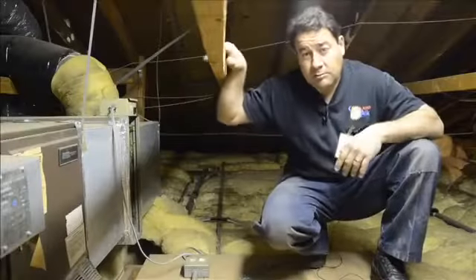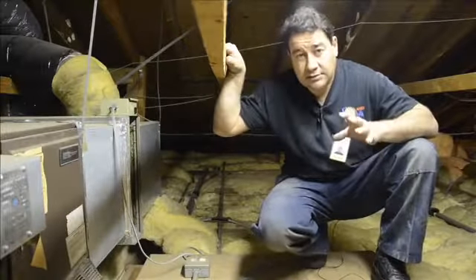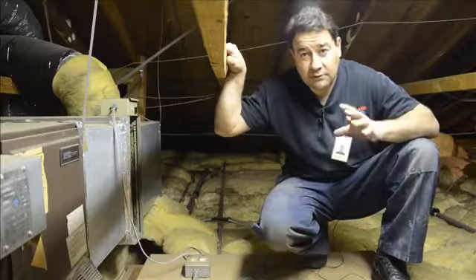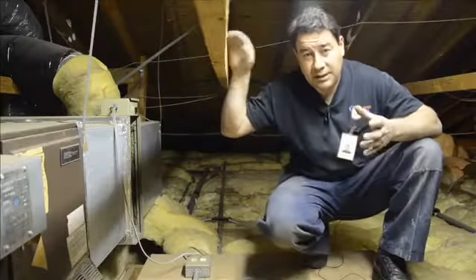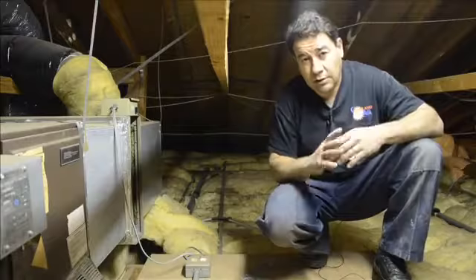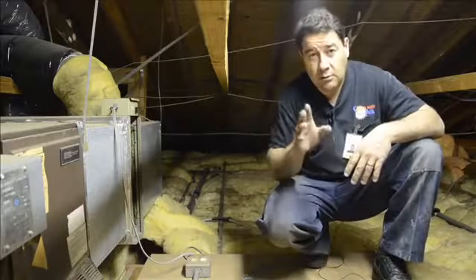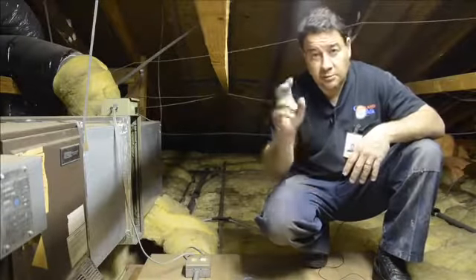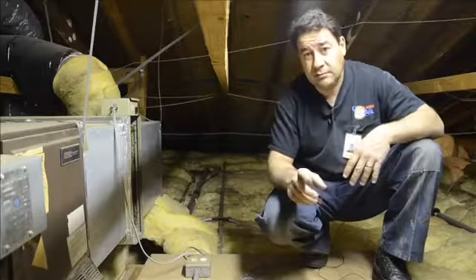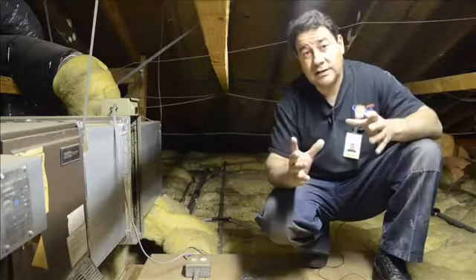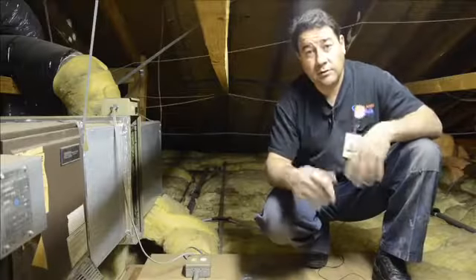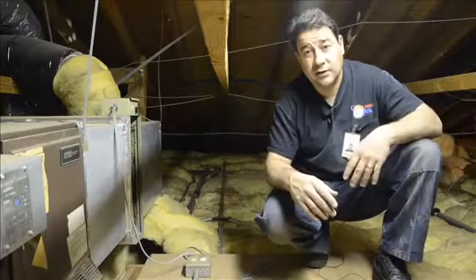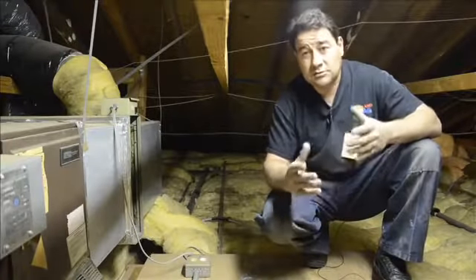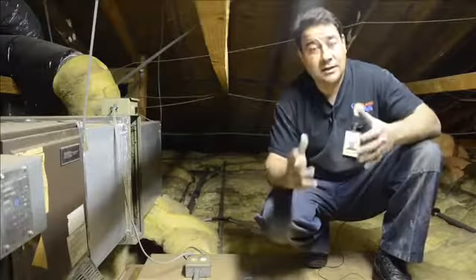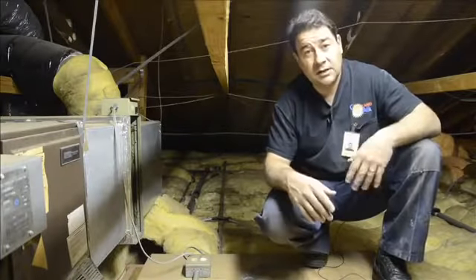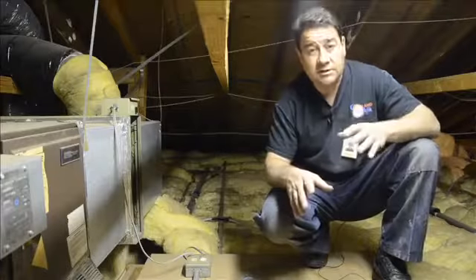All right, the area we're going to be focusing on now is the duct connections, or the plenum, of this furnace and air conditioning system. It's the main mixing box where all the air gets distributed throughout the house. What we've done is disconnected one duct and put a couple of fluorescent lights inside the plenum, so everywhere the light shines through, you'll be able to see where they're losing a big portion or percentage of their air through the duct connections, which was just very common back in the day. They didn't have to seal them. So when we go through with the new system, it'll all be sealed.